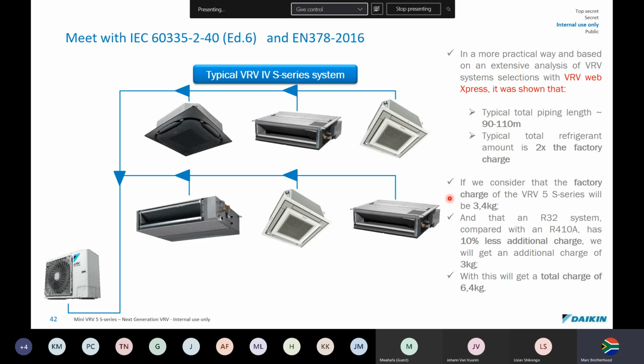So if we consider that the factory charge of a VRV system will be around 3.5 kilos, that is what the factory is going to put into the outdoor unit for you. It will come shipped with 3.5 kilos. And also, an R32 system, when compared to 410, has 10% less additional charge. We will get an additional charge of 3 kilos.